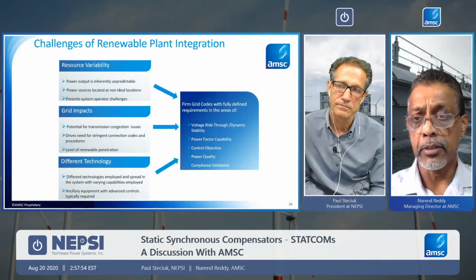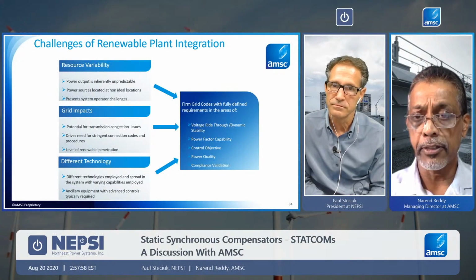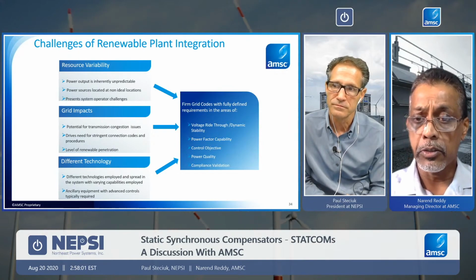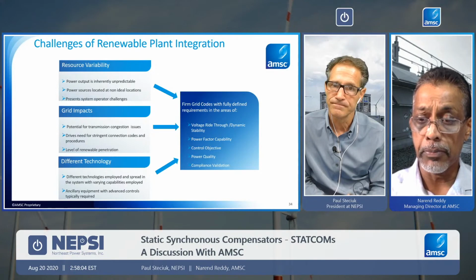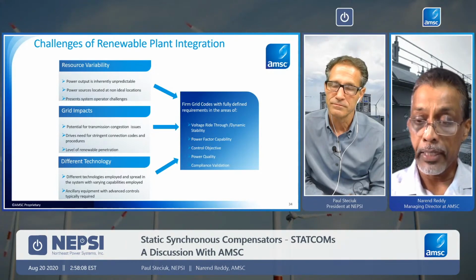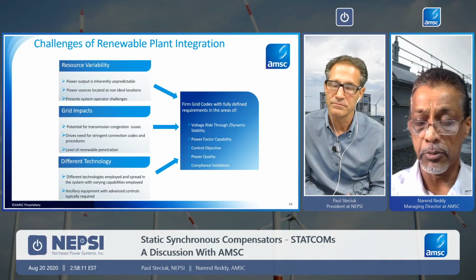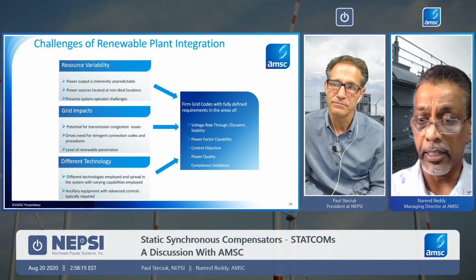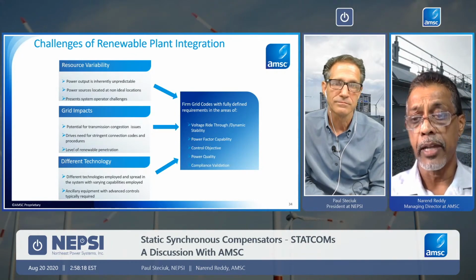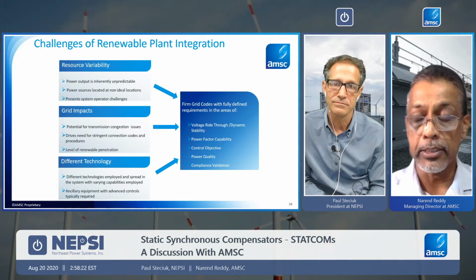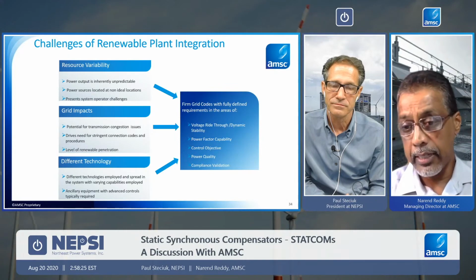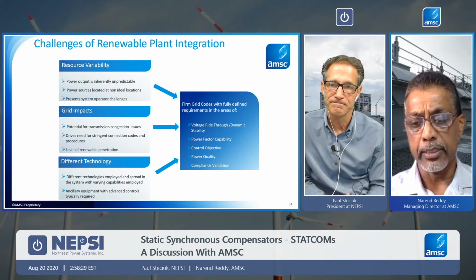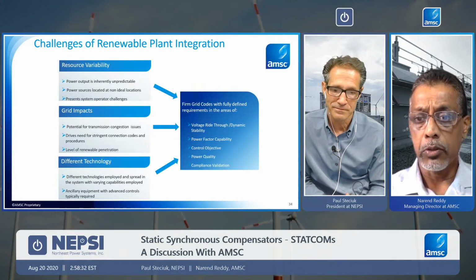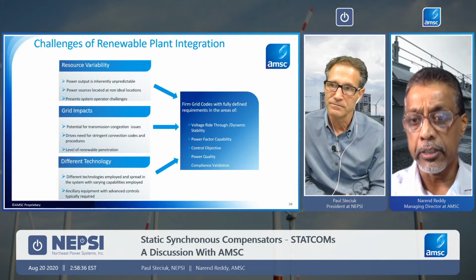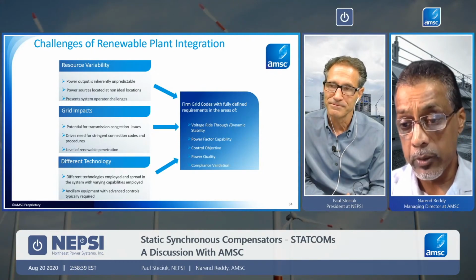So taking all of that into account, typically what we end up with is what we call a grid code. Different regions, different countries, different ISOs have different grid codes that they require these wind plants to meet in terms of performance, whether it's dynamic performance in terms of ability to handle high voltages in the system, low voltages in the system, and if there are additional requirements for these wind plants to support the grid as well, because at some point, these are to be considered as normal power plants if they have to be relied upon. So grid codes are defined, and as you can see, grid codes really clearly specify what performance is required.